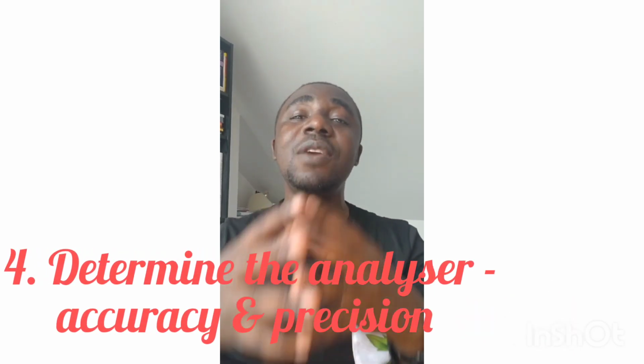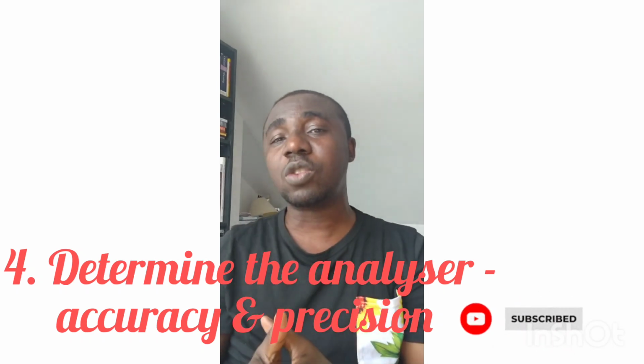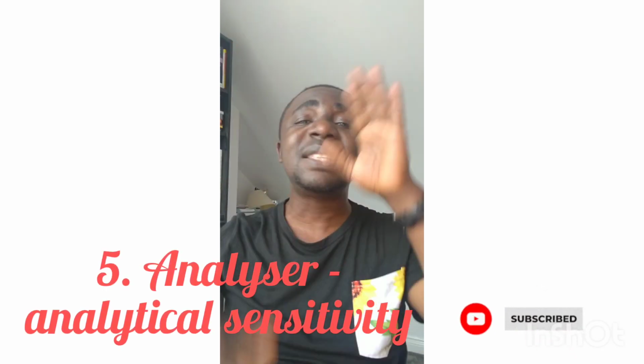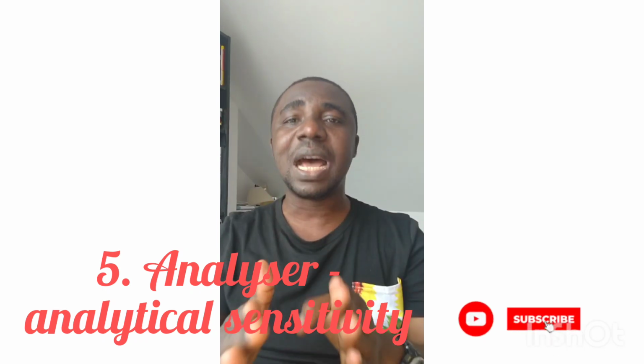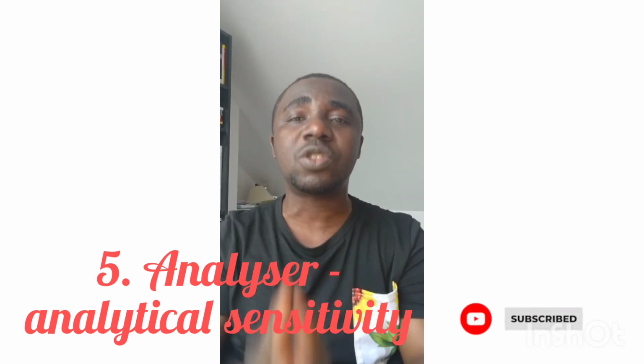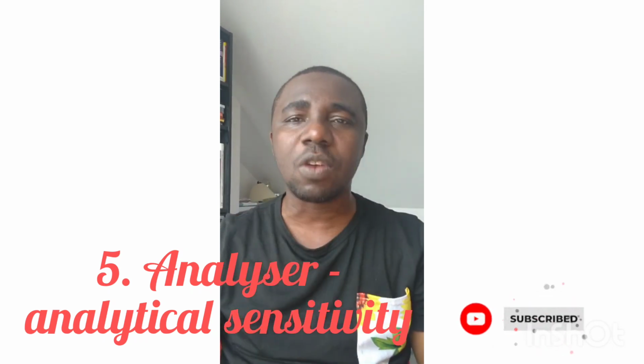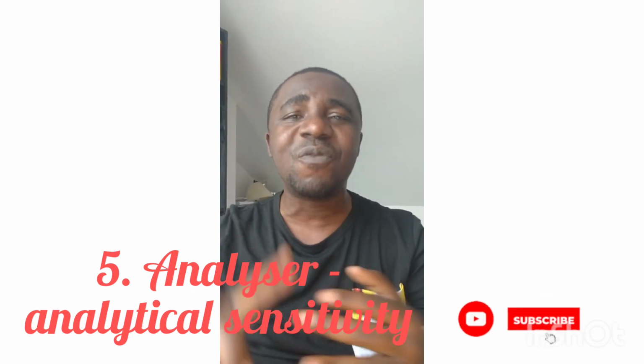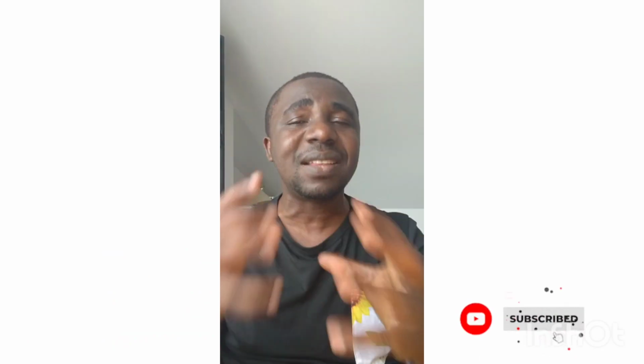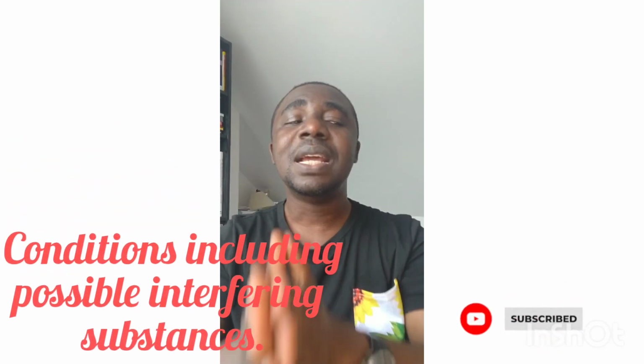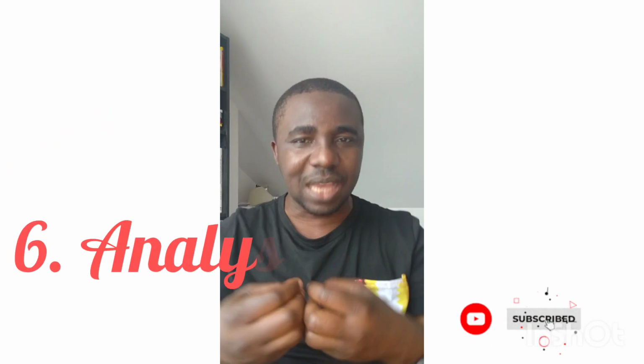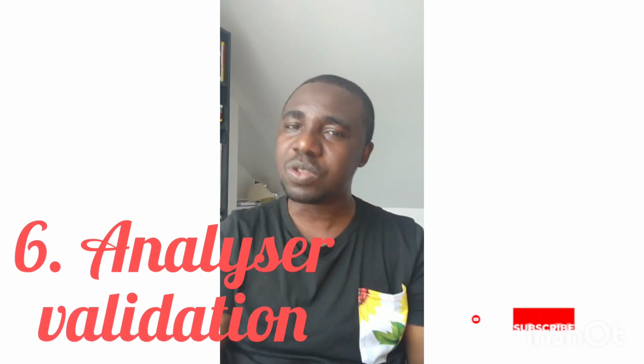You will determine if your quality control has passed, because the quality control has high, low, and normal control samples. You can then determine the sensitivity of that analyzer by running all kinds of patient samples on it, different kinds of patients, both normal and deranged samples. Once it gives you consistent results showing it is sensitive to all kinds of conditions and results, the next thing to do is accept that the analyzer can be used, and that is validation.